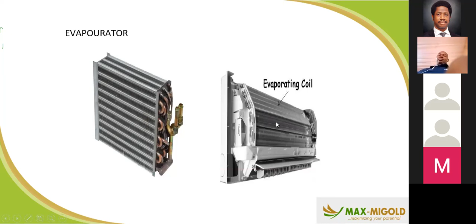Then in front of it, there's a thermostat, a temperature sensor, that is always put there. This temperature sensor senses what is going back into the AC unit itself. Then common problems with the evaporator coil: a blocked coil, or low refrigerant gas. If there's low refrigerant gas inside, sometimes you see ice forming on the evaporator. The same thing can also happen in your condenser coil. You just see ice forming, or some white thing, while the AC is working.